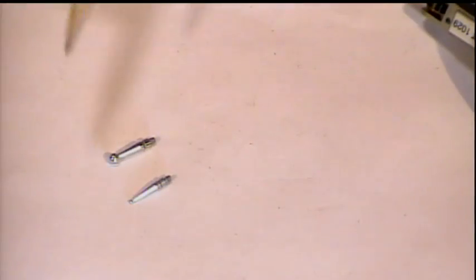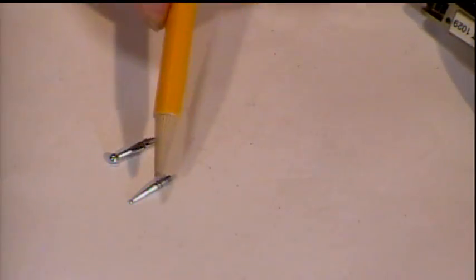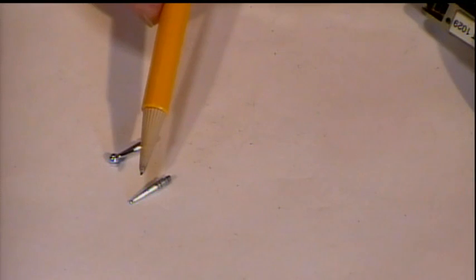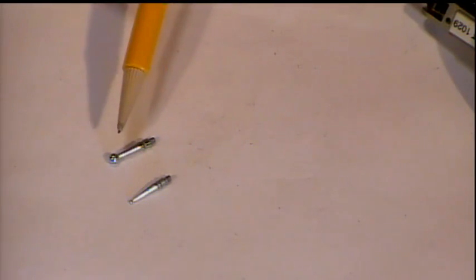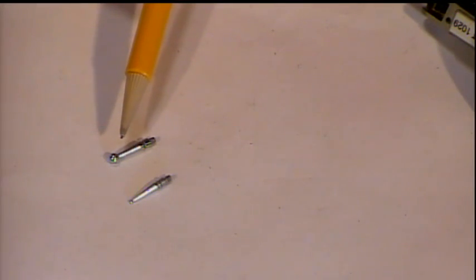Some will have flats on the bottom and top, and they need to be replaced when that happens. Now, what about ball size - does it matter? You've got one with a very small ball on the end and one with a rather large ball, BB sized. That's interchangeable - the user determines what they need. Some need to get into a tight place and want a small one, others are measuring a large surface and want a larger ball.